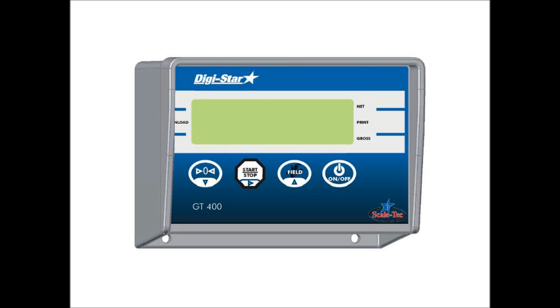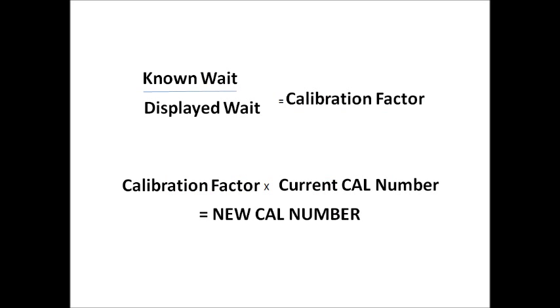The next step in this procedure involves adjusting your calibration number. The indicator will then display C-A-L for Cal. To adjust your calibration number, you'll need to know your known weight, so certified weight, divided by the displayed weight of the indicator, which will then equal your calibration factor.